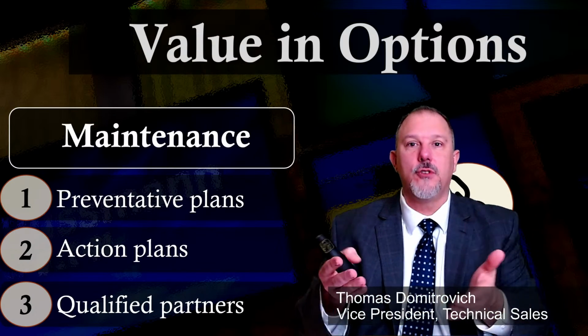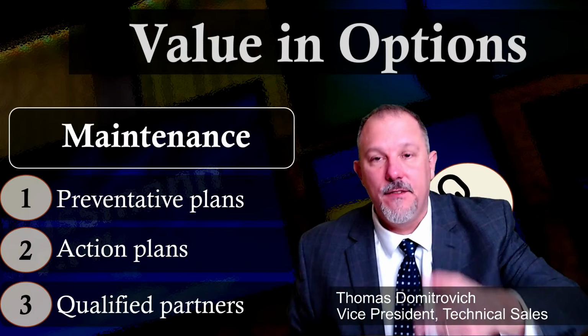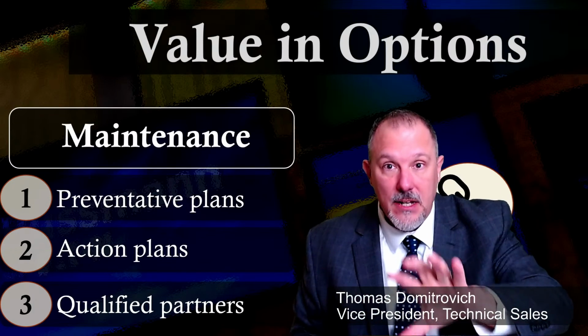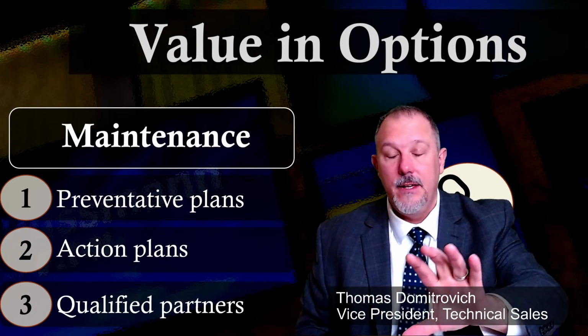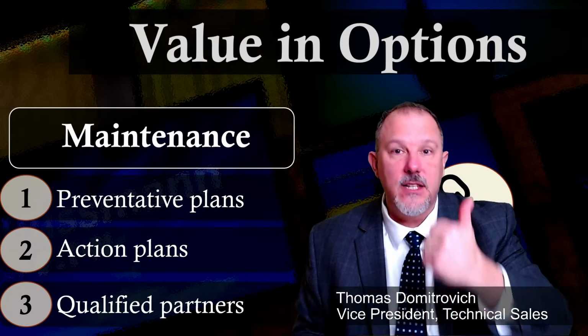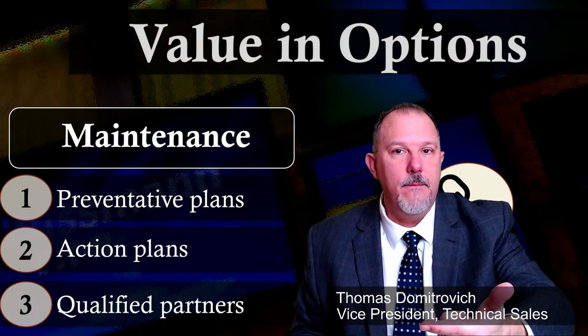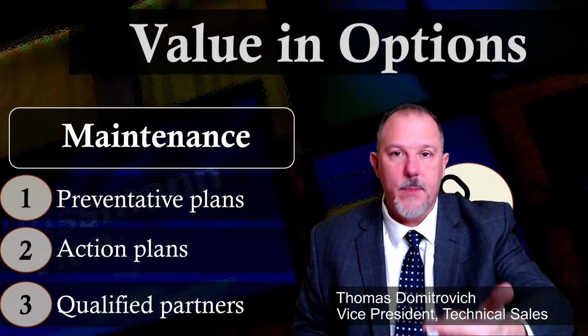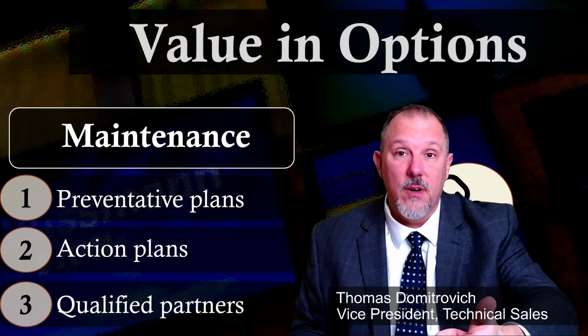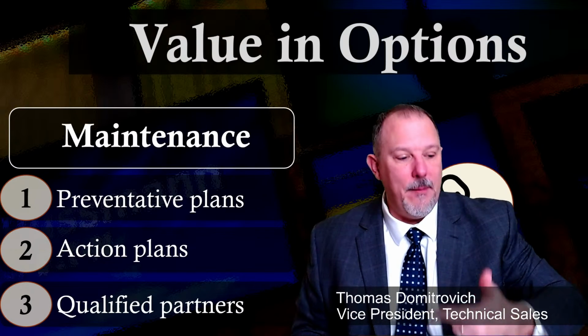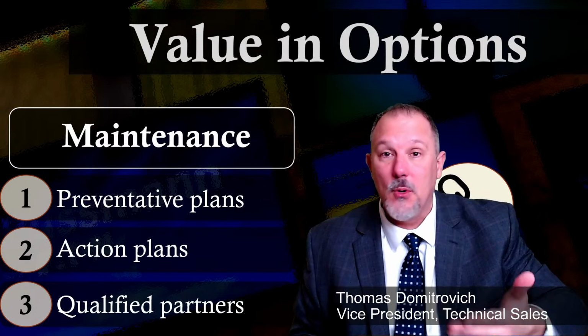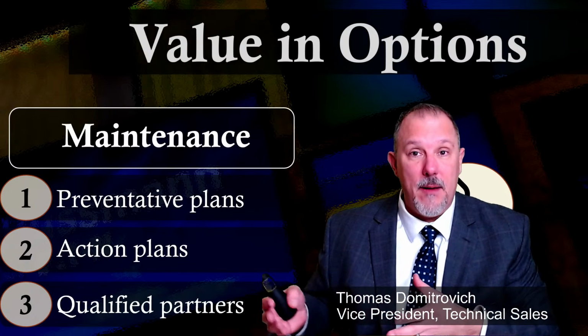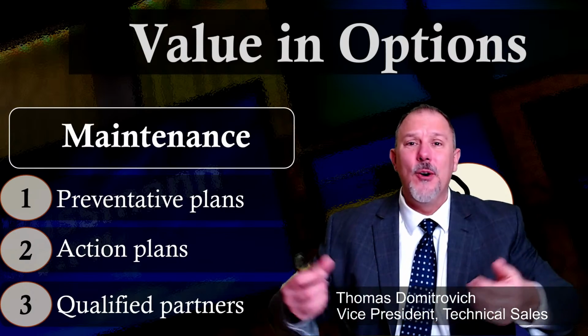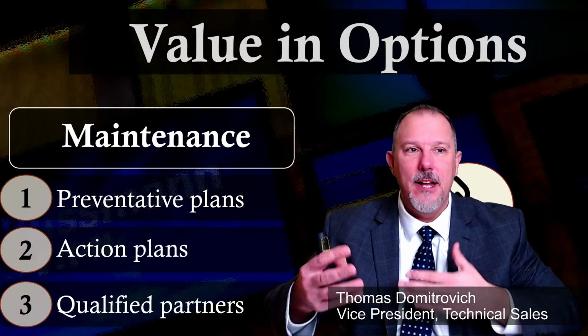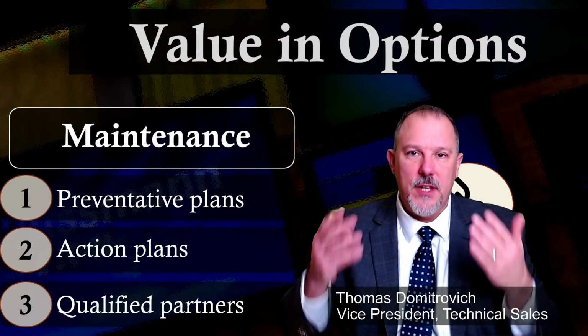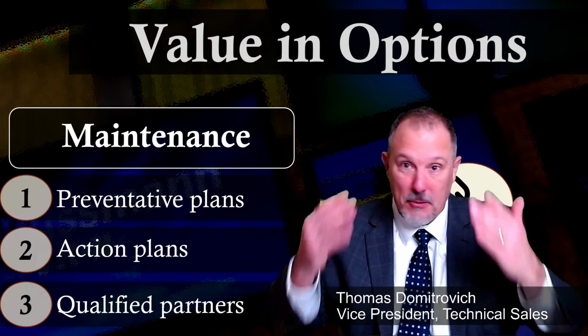This is going to help in your maintenance plan, your preventative maintenance. If you can go to your circuit breaker and say, what's the health of this device, I should be pulling maintenance on this one because it's seen a lot of activity, interrupted not bolted fault currents but a decent number of heavy currents. It might be time to pull maintenance on it before you get a problem. You'll know what you need to get, so you swap it out. You reduce your downtimes, you increase your uptimes, your productivity times.